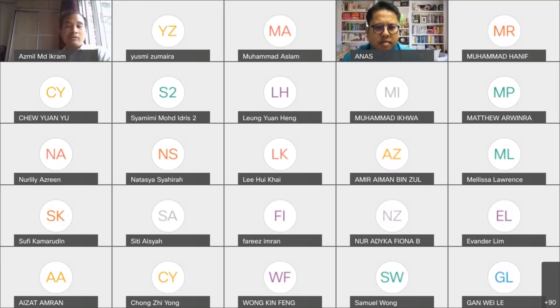But usually they go with running hours. So your uptime is based on running hours. They clock it and say, okay, now it's already 2,000 hours, we'll do a minor service. And then it goes on every 2,000 hours. It takes only one day, 8 hours to be exact. It's just like changing the engine lube oil. That's it. And in between you check on a few other things in the systems.